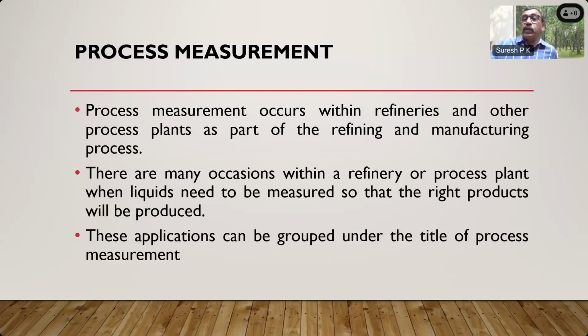Then process measurement comes. Process measurement occurs within refineries and process plants, like a power plant. You want to know the boiler feed water going into the boiler drum, which is critical for the operation of the boiler, so you need a flow measurement of that water. It is not as critical as in custody transfer applications, but it is still critical from the operational point of view. So process measurement is different from custody transfer measurement. There are many occasions within a refinery or process plant where liquids need to be measured so that the right products are produced, because some mixing can take place. Flow rate has to be maintained, or for process safety, the flow rate cannot go above a certain limit. These applications can be grouped under the title process measurement.